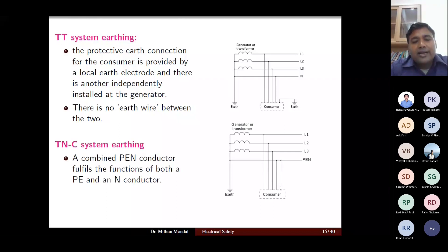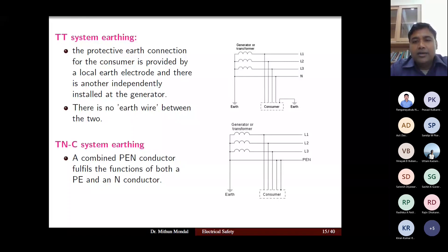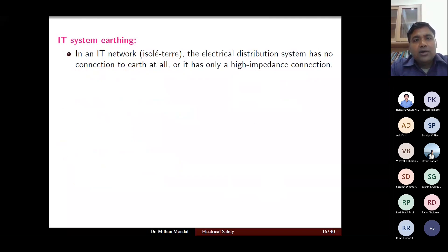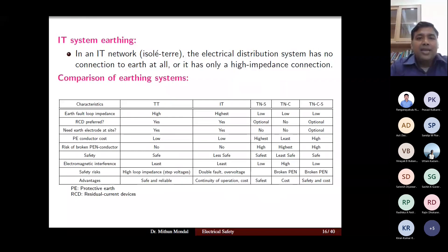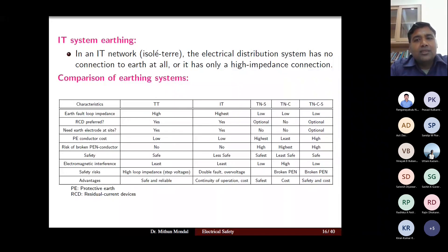The TNC system uses a combined PEN conductor fulfilling the function of both PE and N conductors — there is no separate neutral wire. The IT system — from the French 'isolé terre' — has no connection to earth at all in the electrical distribution system, only a high-impedance connection. IT system is used in very specific applications where earth is not present. Comparing all five systems: earth fault loop impedance is high for TT and IT, and low for TNS, TNC, and TNCS.